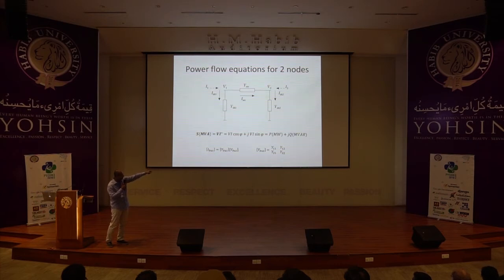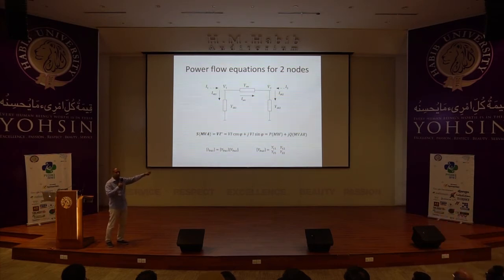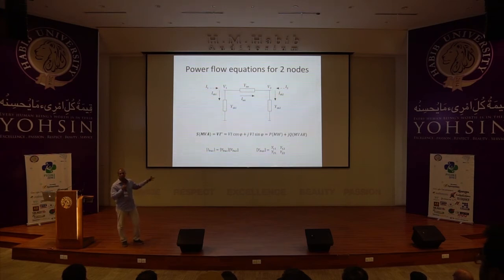So there's one component which is active power, which you pay for, and the other component, Q, which is reactive power, and the only person who has to worry about that is the system operator. It's because without that, you cannot actually deliver the P. Without the Q, you can't deliver the P. You don't pay for the Q, but you have to have the Q in the system because you can't get the P without it. So why am I talking about all this? I have a point, trust me. Okay, I'm going to get there.